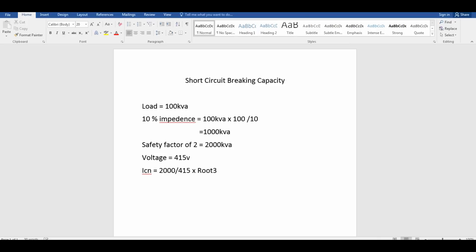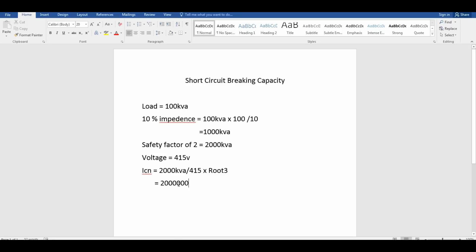So ICN equals 2,000 divided by voltage into root 3, that is 1.732. That is 2,000 kVA times 10 to the power 3, divided by 415 into 1.732. This gives approximately 2.78 kA. This is a good demonstration for the calculation case.